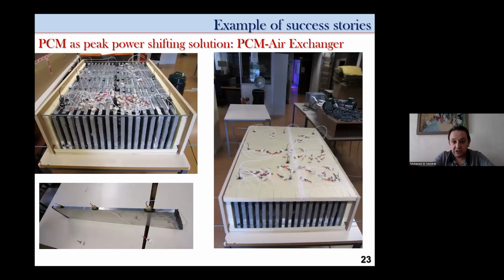The heat exchanger looks like this: it's a parallelepiped heat exchanger with several plates. Inside the plates we put paraffin that melts at 35 degrees. Between the plates we have aluminum fins to enhance the heat exchange. The idea is to store thermal energy in the phase change material, the paraffin, during the day, and only use ventilation, not heating, to retrieve this energy during the peak power period.